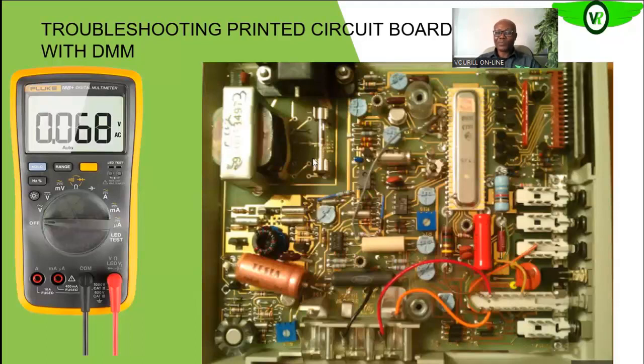Or if you keep blowing the fuse, it means that the rectifier circuit is already bridging. That is when the fuse will be blowing every now and then, especially if the transformer is good. So if the rectifier circuit is good, then you can do your voltage tracing on each of these terminals.